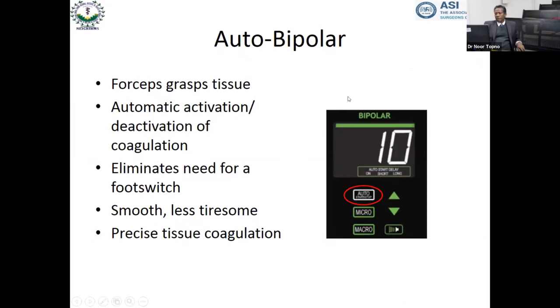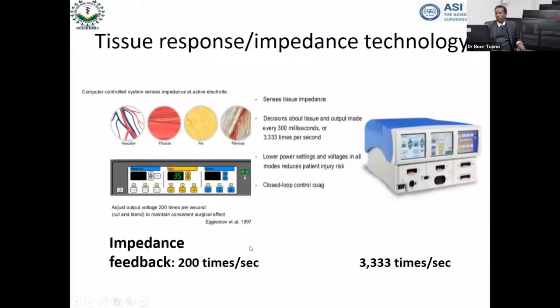Now, one more safety measure is the auto bipolar mode. The good thing about the auto bipolar mode, which you see here, is that the moment the grasping forceps grasp tissue, the bipolar mode kicks in. You don't have to press a separate foot switch. So here it eliminates the need for a foot switch. So usually it is a smooth and effortless exercise, and precise coagulation usually happens.